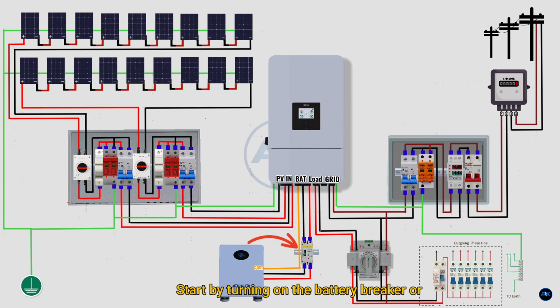Start by turning on the battery breaker or isolator. The battery will power up the inverter's internal electronics, and the DEYE hybrid inverter should boot up automatically. Allow the system a moment to initialize and perform its self-check. Once initialization is complete, we can bring the PV system online.